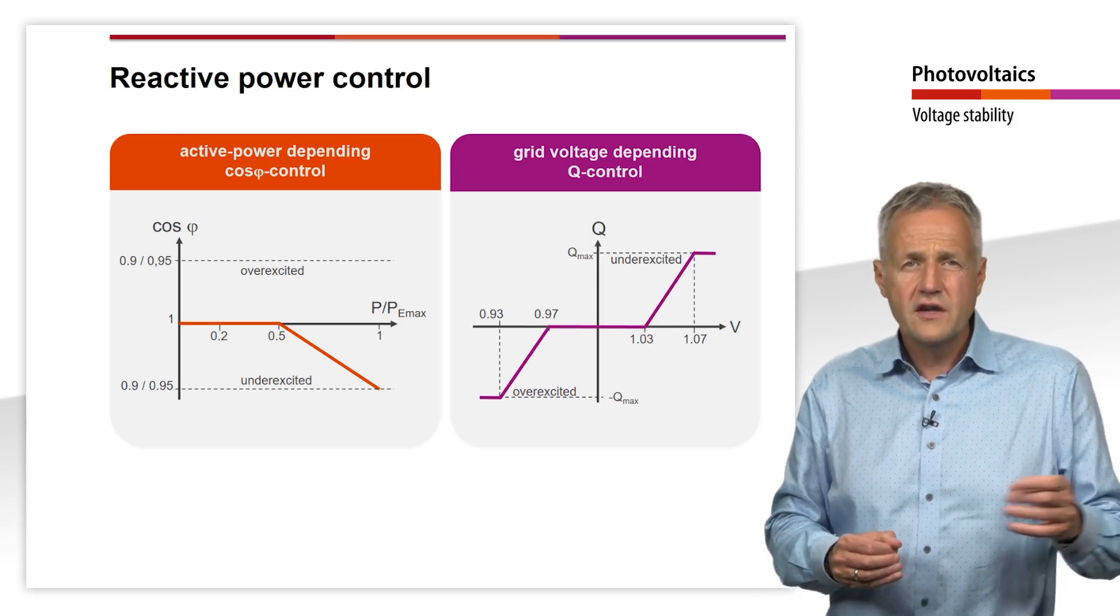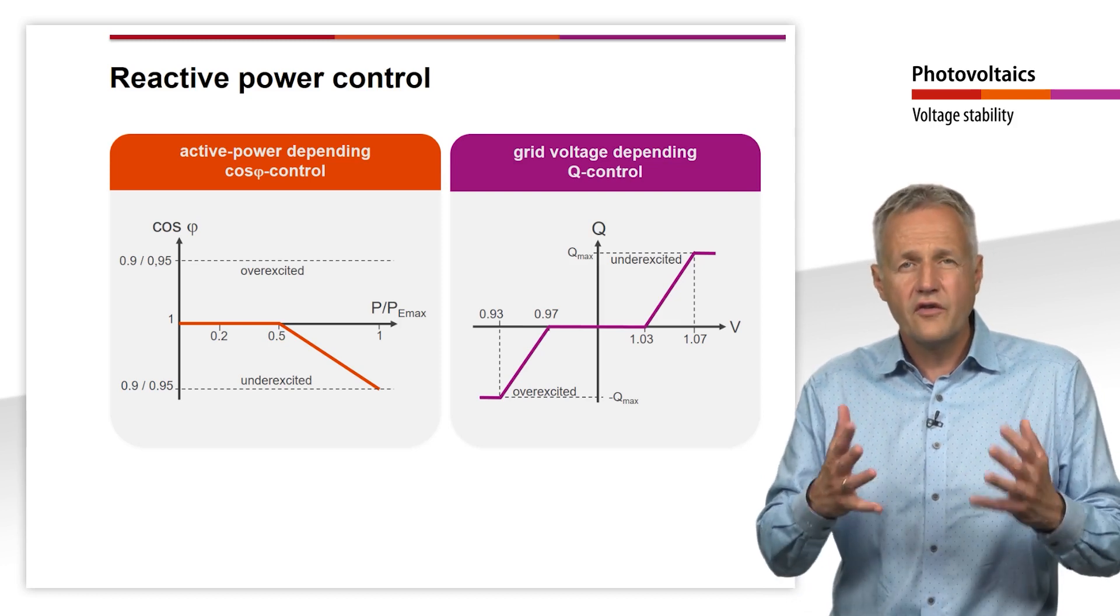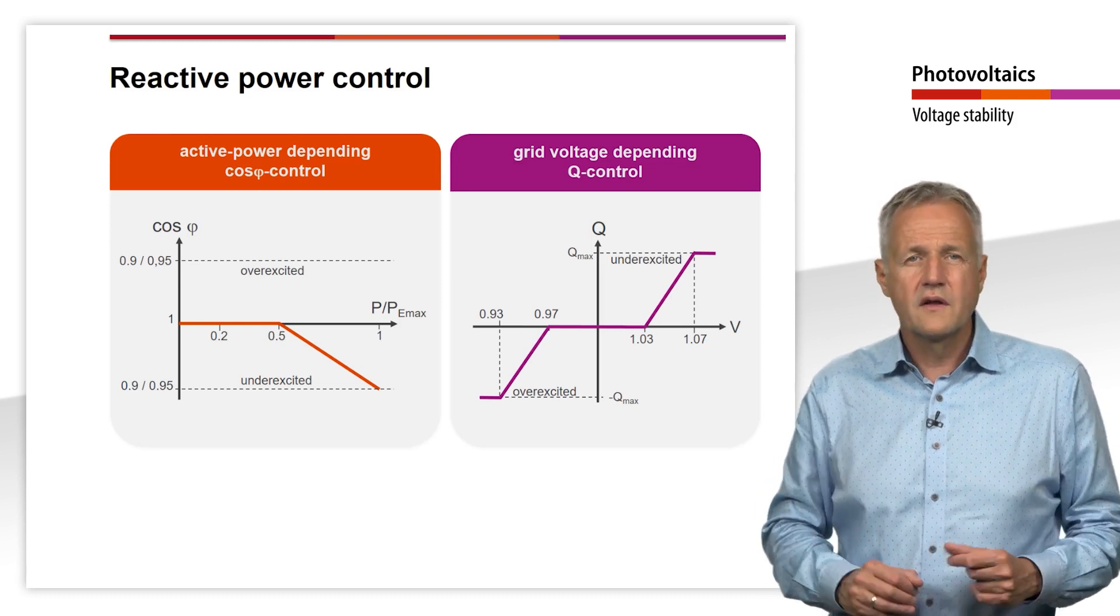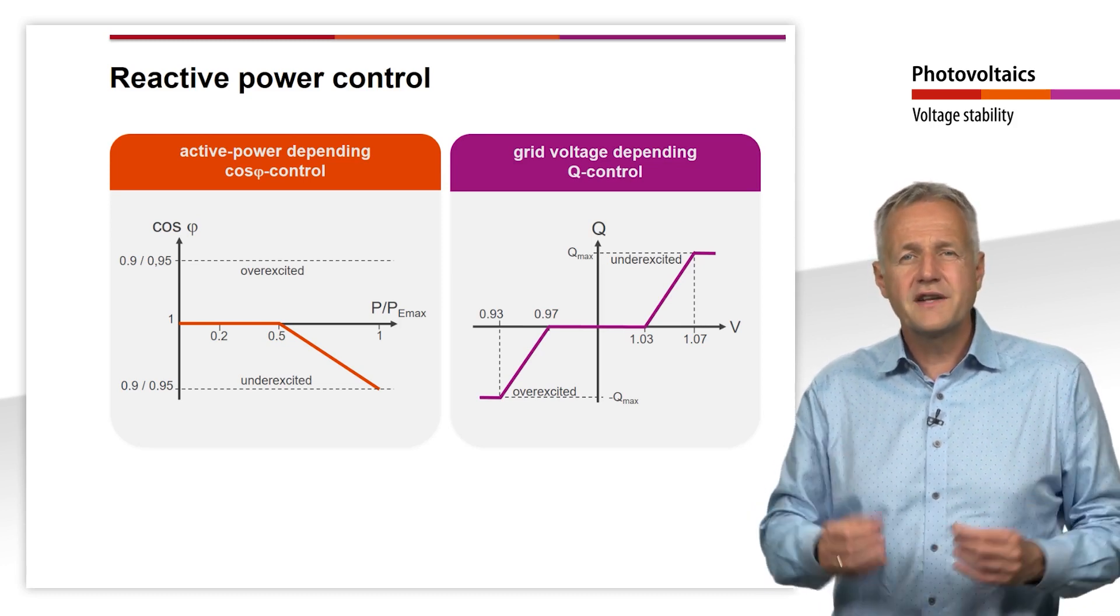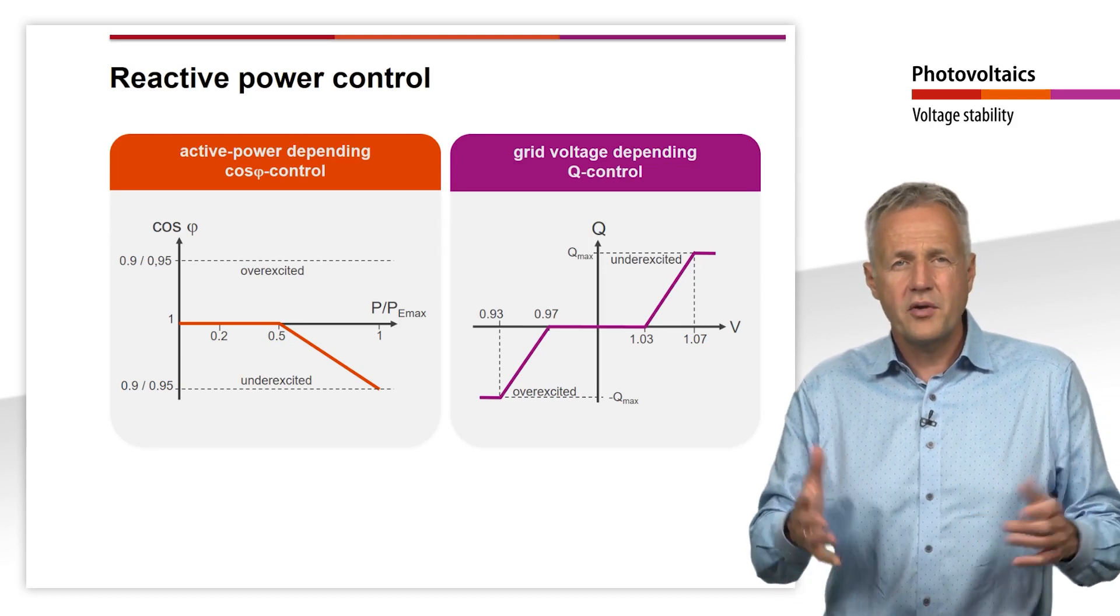The advantage of QV control is that the PV systems can also contribute to voltage stability when the grid voltage is too low. In Germany, the grid operator decides which method is to be used by a plant.